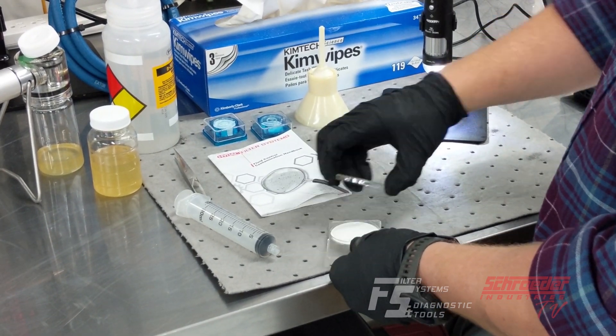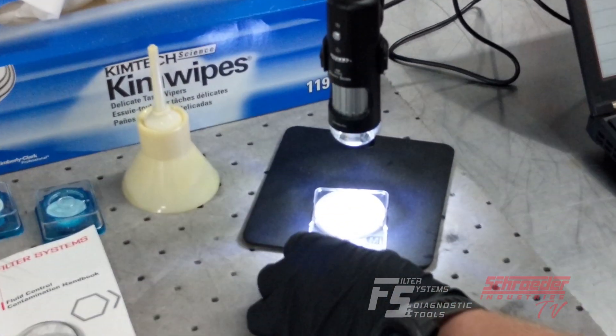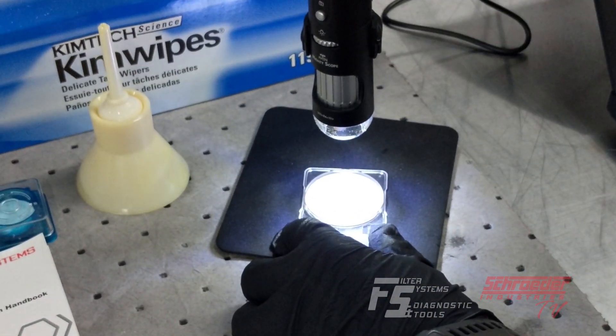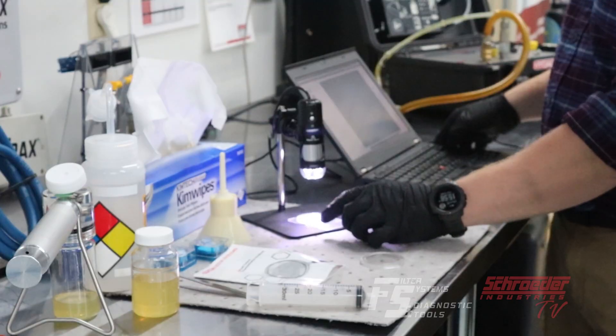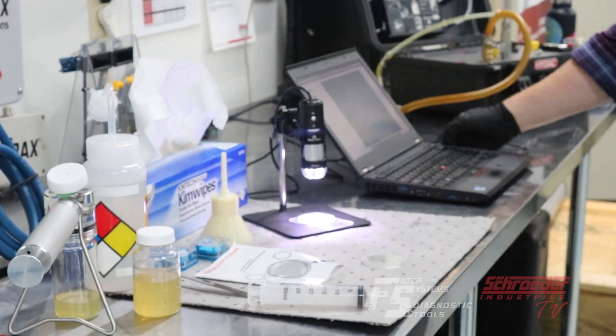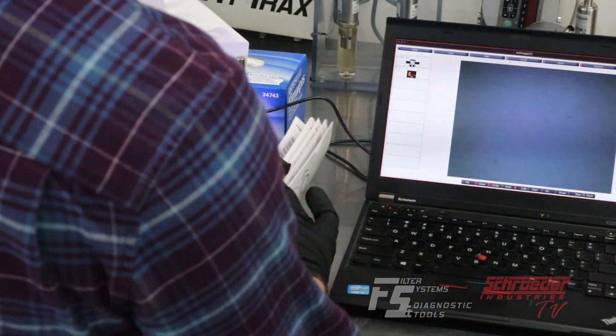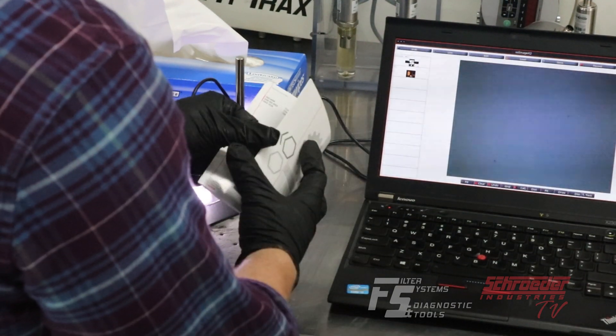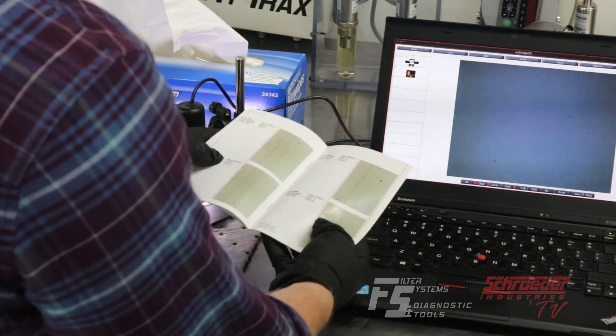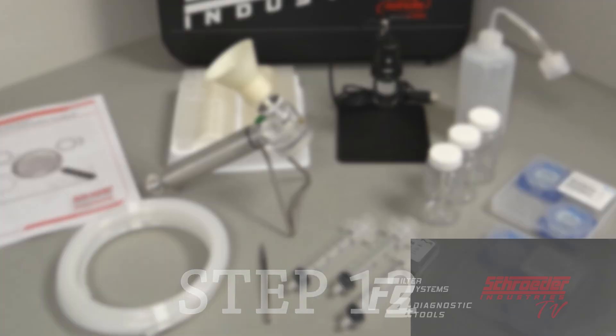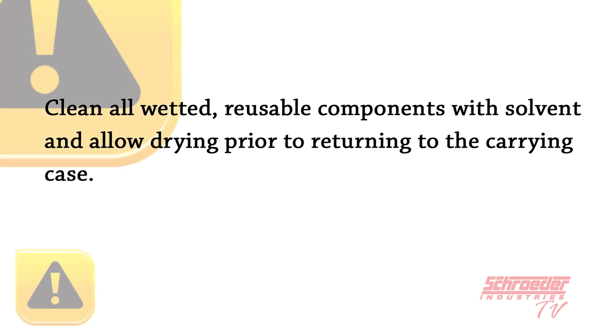Step 11: Examine the contaminated fluid patch with the digital microscope and analysis software. Refer to the fluid control contamination handbook to determine the nearest representative contamination distribution image. This will be the estimated cleanliness of the sample. Step 12: Clean all wetted, reusable components with solvent and allow drying prior to returning to the carrying case.